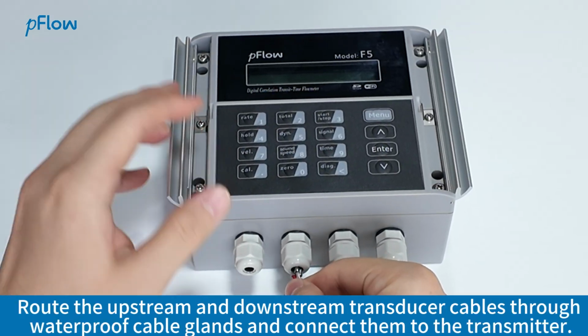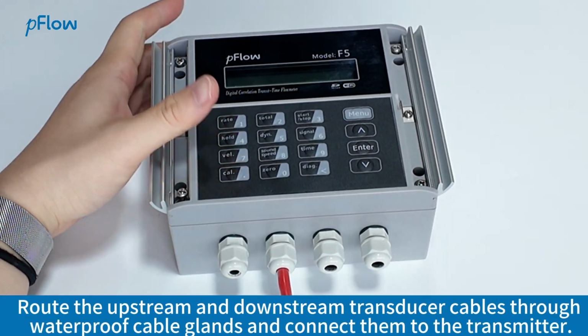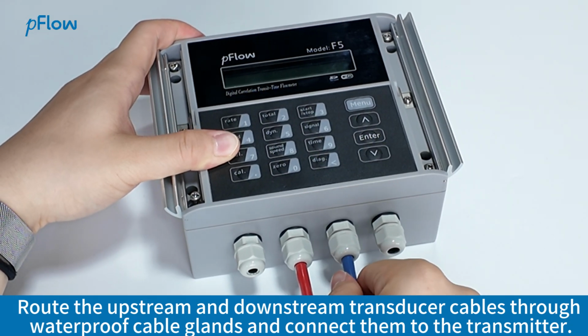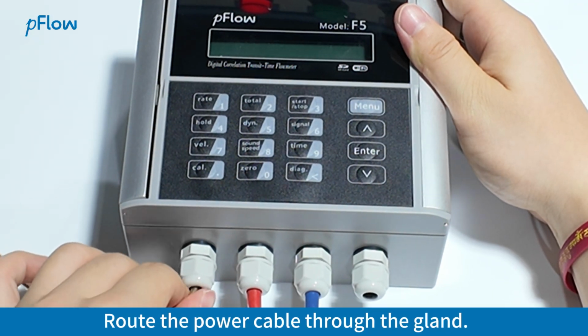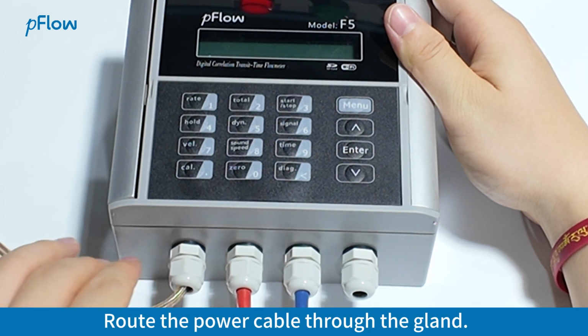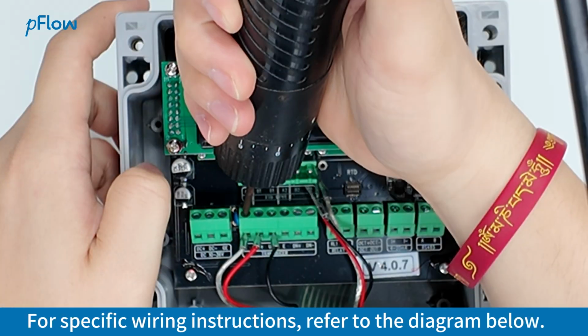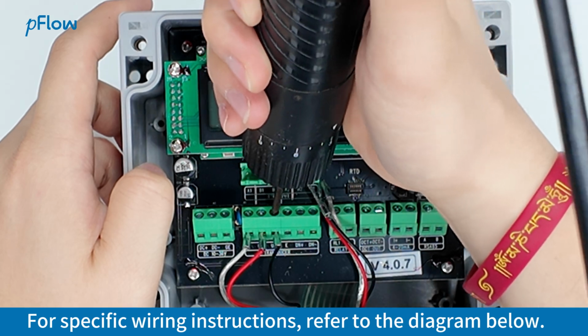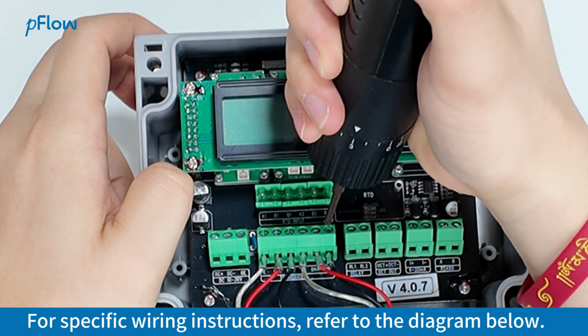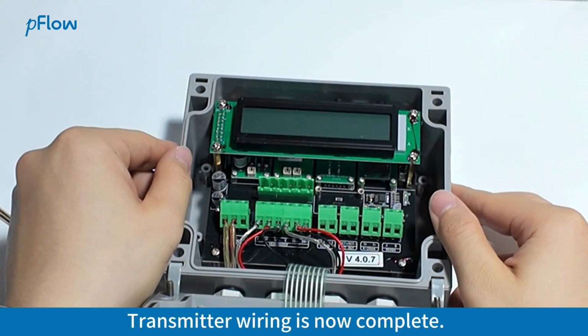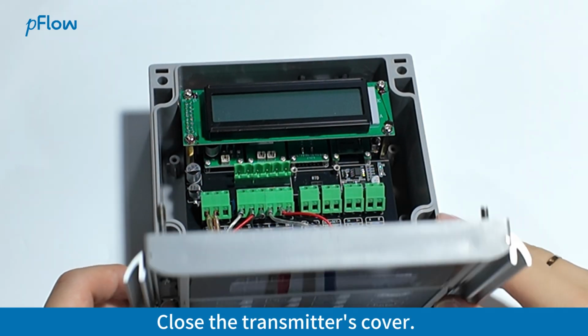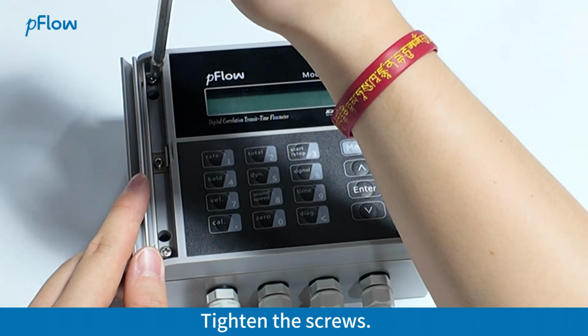Route the upstream and downstream transducer cables through waterproof cable glands and connect them to the transmitter. Route the power cable through the glands. For specific wiring instructions, refer to the diagram below. Transmitter wiring is now complete. Close the transmitter's cover. Tighten the screws.